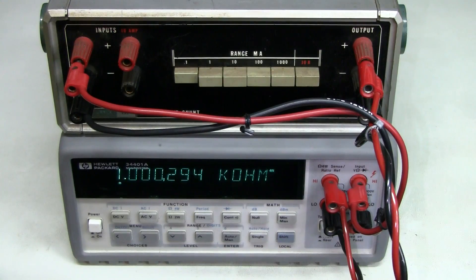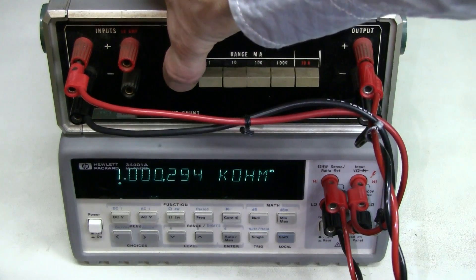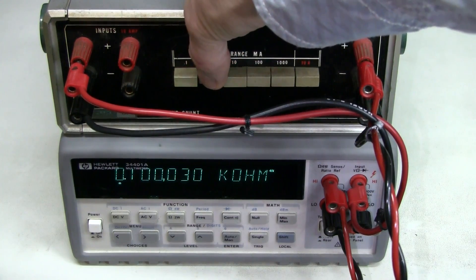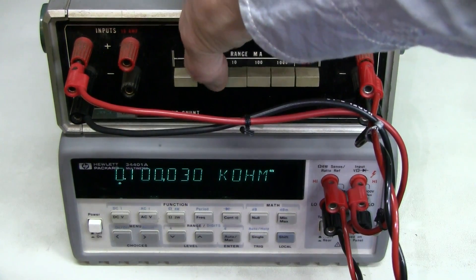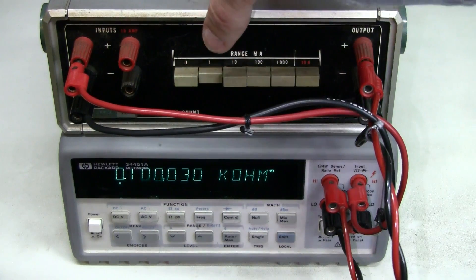The cleaning is done. Now let's see if I wiggle this switch — we have a stable reading. I showed before that when I was wiggling the switch the reading went all over the shop; now it is stable and nothing changes at all. Excellent.